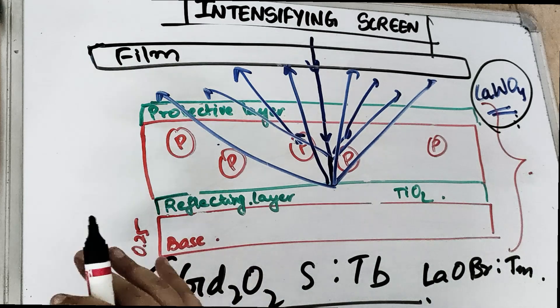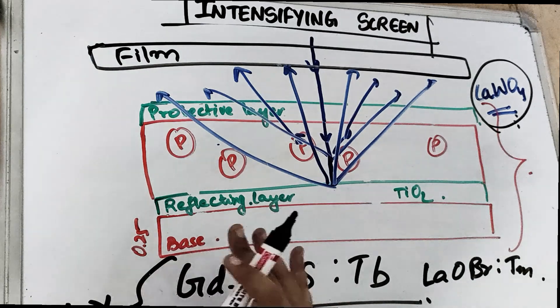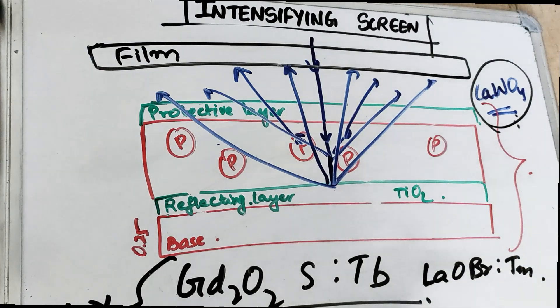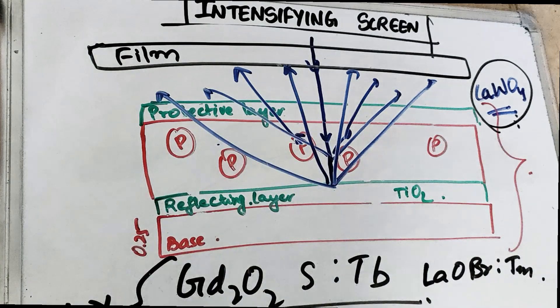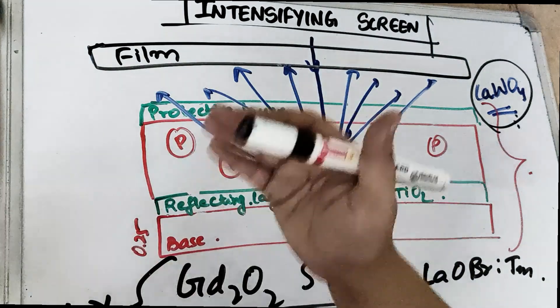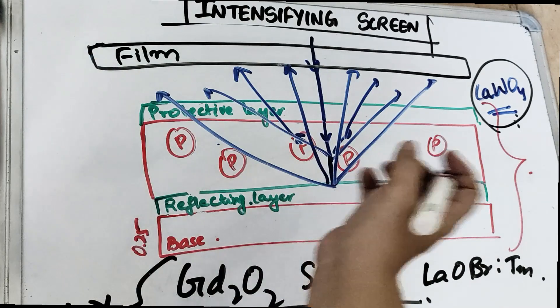Some recent IOPR also use rare earth intensifying screens, which consist of terbium-activated gadolinium oxysulfide and thulium-activated lanthanum oxybromide. Now that you know everything about the intensifying screen — we use it for extraoral radiographs, panoramic radiograph (OPG), cephalometrics, skull radiograph. Why don't we use it in IOPR? Because there is a loss of resolution with their use. It is also very important that we keep this intensifying screen clean — if any debris, spot, or scratch is there, it will make light spots on the image.